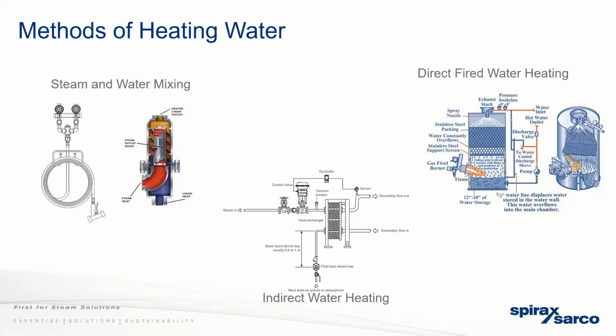Another method that we would typically use is indirect water heaters. The benefit here is you're separating the plant steam, with all the boiler chemicals and any of the rust and scale found in the pipework, from the potable water on the process side. This way you take away those risks, and you're still using potable water to contact your food contact surfaces.